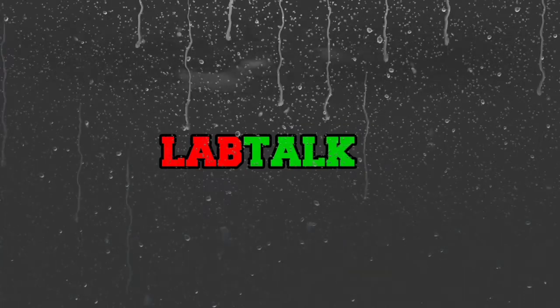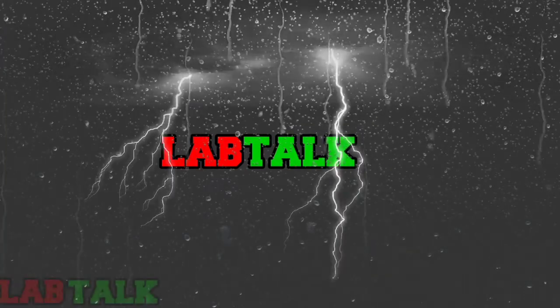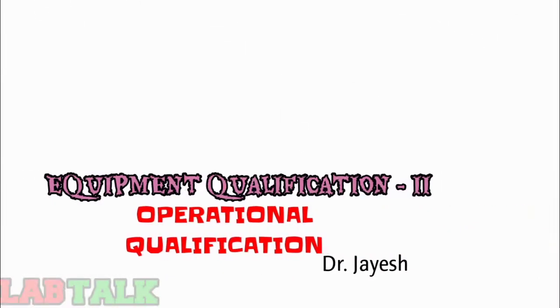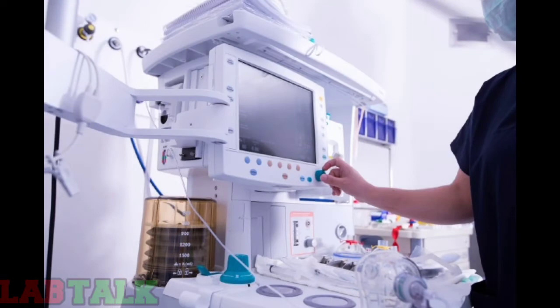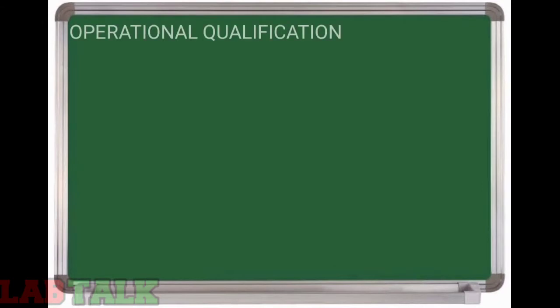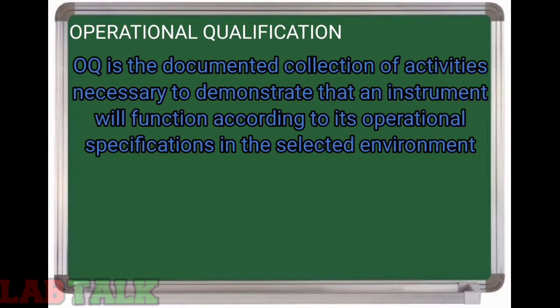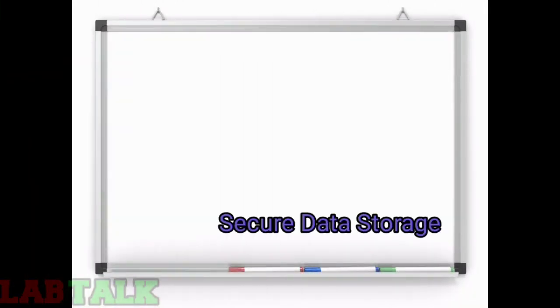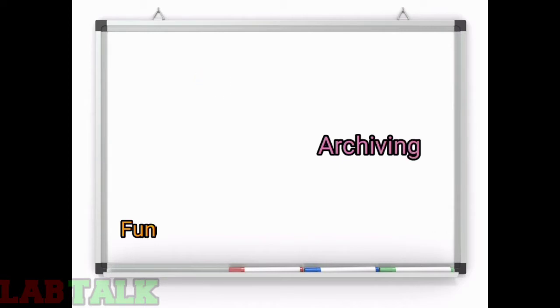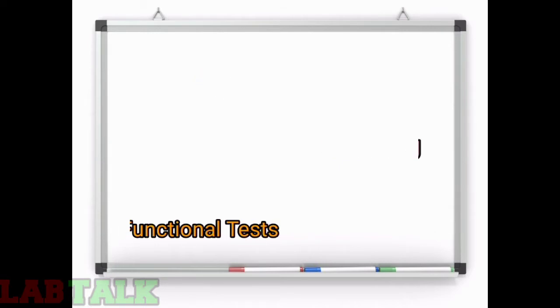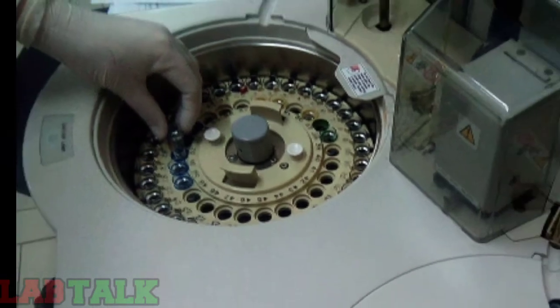Hello friends, welcome to LabTalk. This is the second video in the series of equipment qualification. Coming to OQ, or the operational qualification — after successful IQ (installation qualification), the instrument is ready for operational qualification. OQ is the documented collection of activities necessary to demonstrate that an instrument will function according to its application in the selected environment. This documentation includes secure data storage, backup, archiving, and functional tests. The vendor or user must perform this qualification.